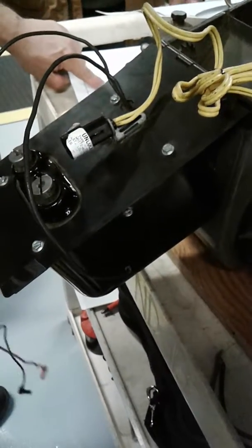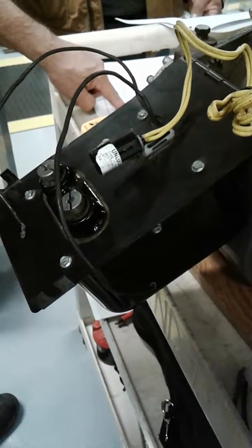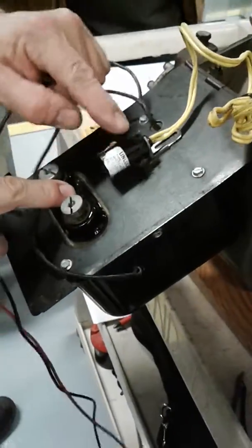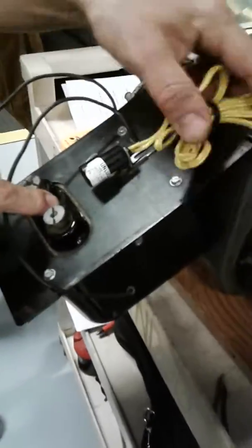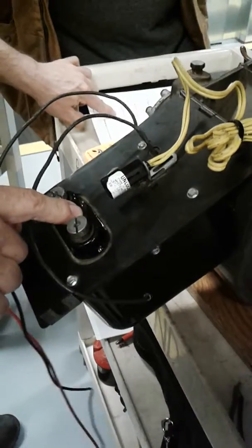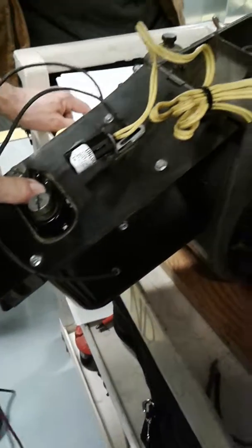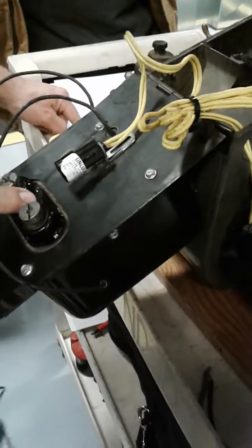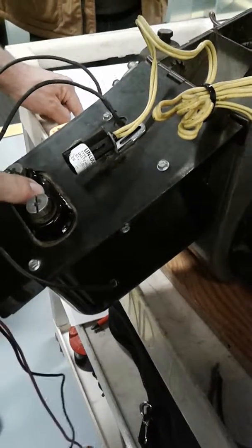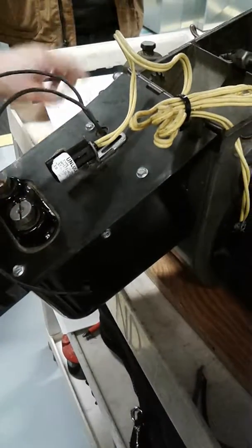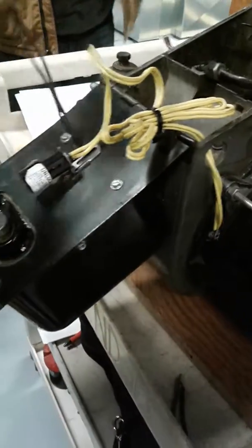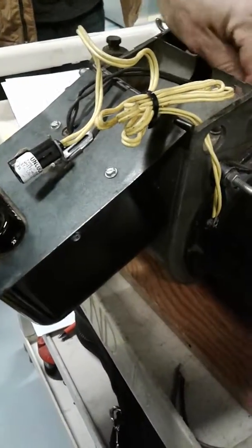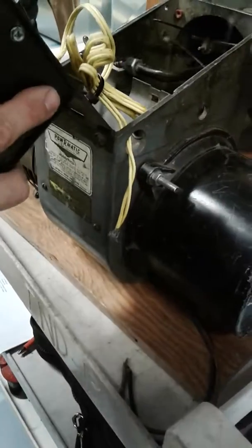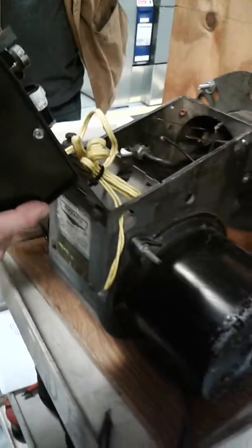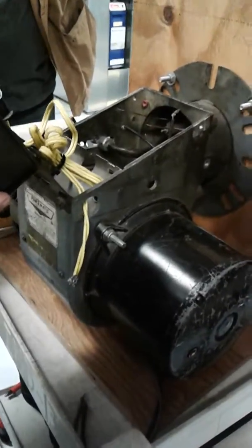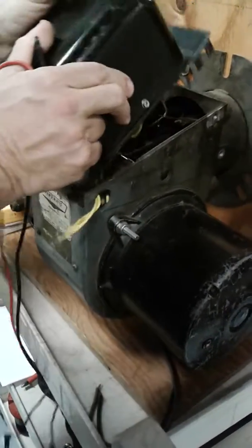Check the continuity of the CAD cell on the oil furnace. This is the CAD cell right here. This device right here, hooked up to the yellow wires. What is the resistance of the CAD cell with no flame? No flame. Okay? No flame means in total darkness. There's no flame. So, what that means, guys, is this. Right now, we're reading a different type of resistance because we have light. That is considered the flame. Okay? We are going to close this.